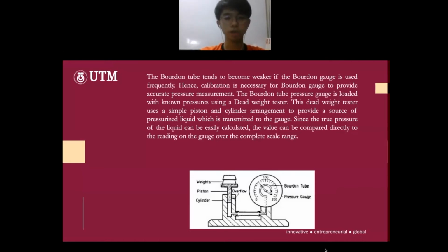The Bourdon tube pressure gauge is loaded with known pressures using a dead weight tester. This dead weight tester uses a simple piston and cylinder arrangement to provide a source of pressurized liquid, which is transmitted to the gauge. Since the true pressure of the liquid can be easily calculated, the value can be compared directly to the reading on the gauge over the complete range.